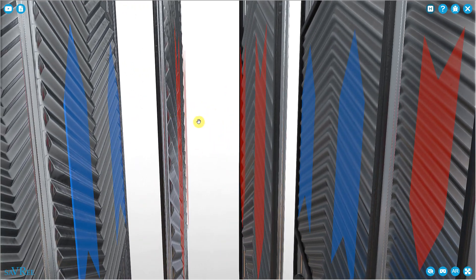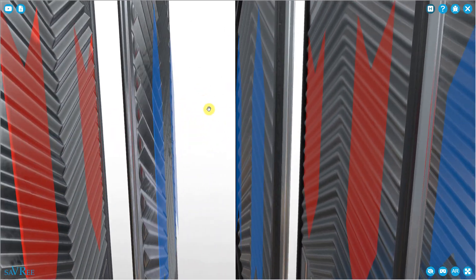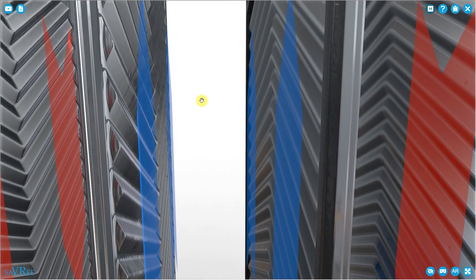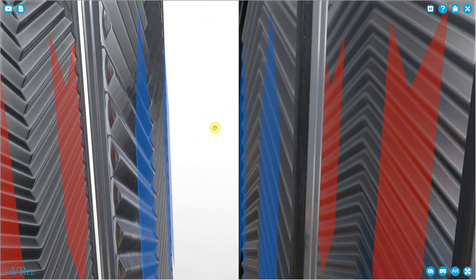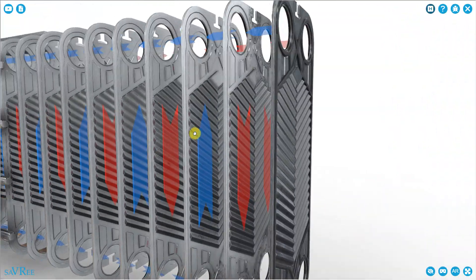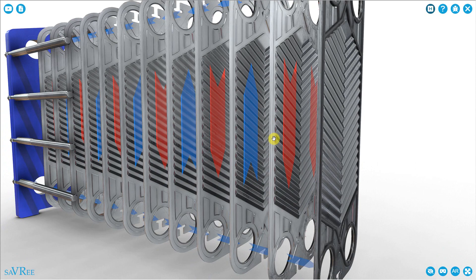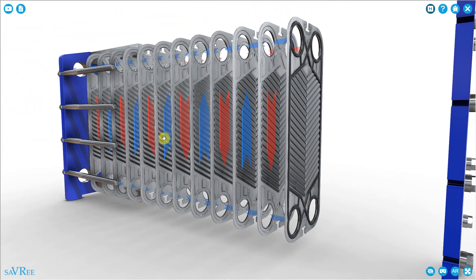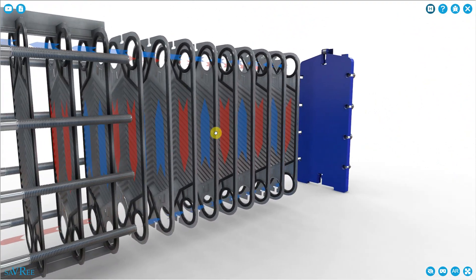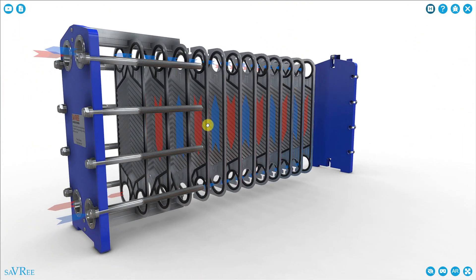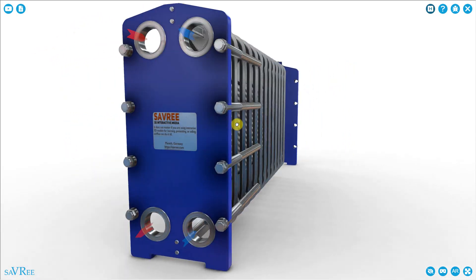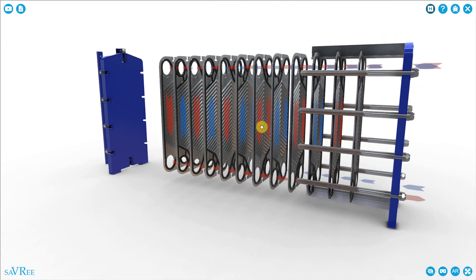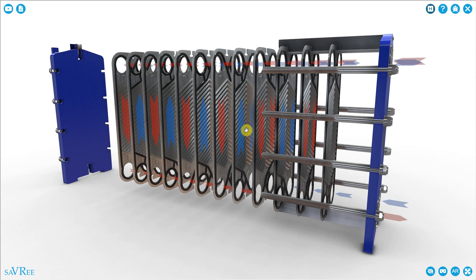This is a thin metal plate where my mouse is, and there's a series of them. You can see we've got red fluid here, then blue fluid. Zooming in to make it easier: blue fluid flows between these plates, then red, then blue, then red. In this way, heat can be conducted through the metal and pass from one fluid to another. Contact surface area is critical for heat exchangers to ensure a good heat transfer rate. Engineering designers will always maximize the contact surface area to maximize the heat transfer rate, so that the heat exchanger can be as small and as efficient as possible.